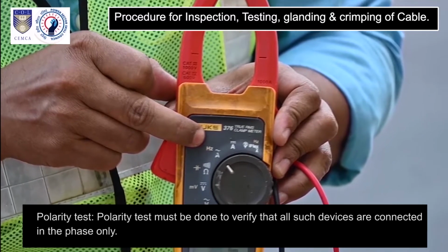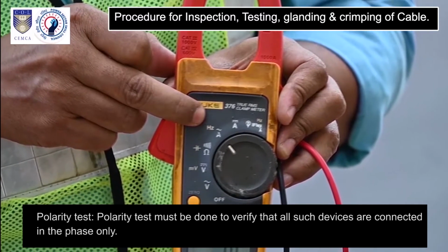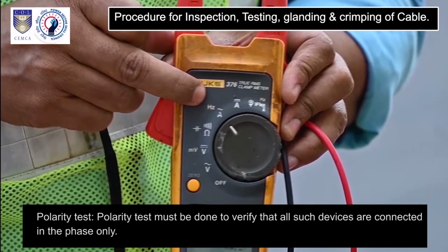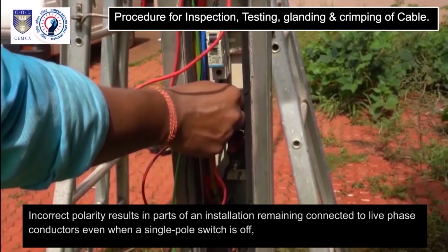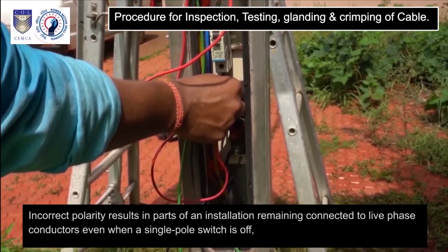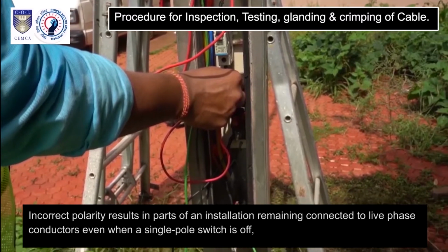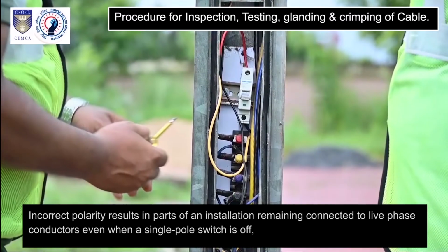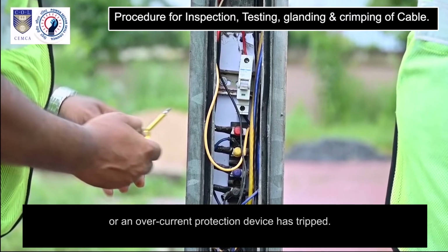Polarity test. Polarity test must be done to verify that all such devices are connected in the phase only. Incorrect polarity results in parts of an installation remaining connected to live phase conductors even when a single pole switch is off or an overcurrent protection device has tripped.